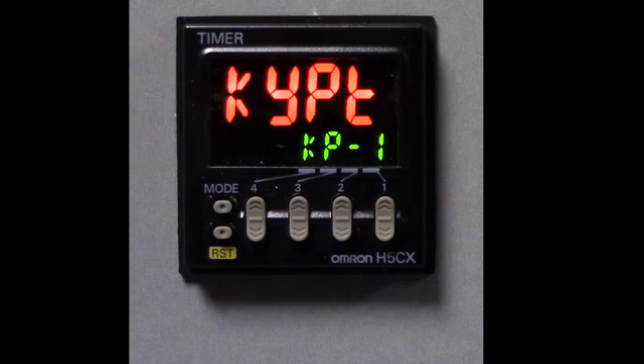Last but not least is the KYPT. This is your Key Protect. There's seven different levels of Key Protect. As I'd mentioned before when choosing your timing sequence, have the data sheet available. I recommend that you have the data sheet available when you are choosing your Key Protect, because depending on which level you choose, you're going to be locking out certain functionalities of the H5CX-N timer. So I'm going to keep it at the factory default of KP-1, because this allows us to have access to everything.